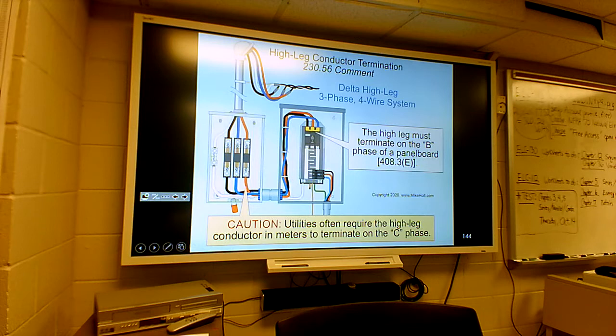Now, when you get to the house or building you're feeding, for some reason they want the high leg to be in the middle. They want it to be in the middle on the L2 phase. I don't know why they didn't just stay in keeping with the third leg there, but they didn't. And you see that difference, and that's what's actually required. You may never see it. You may never deal with a situation like that, but if you do, you will at least have seen it one time in here.